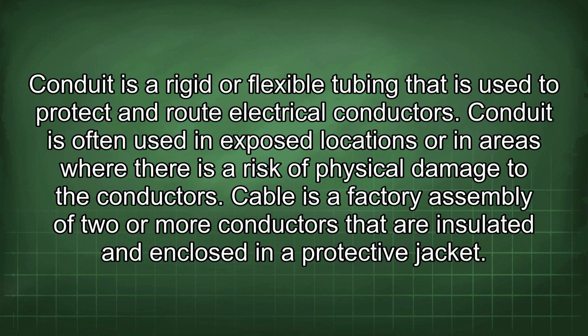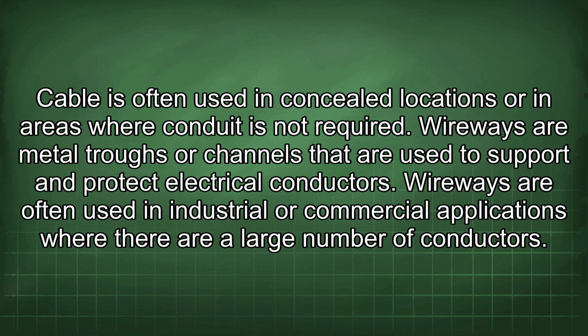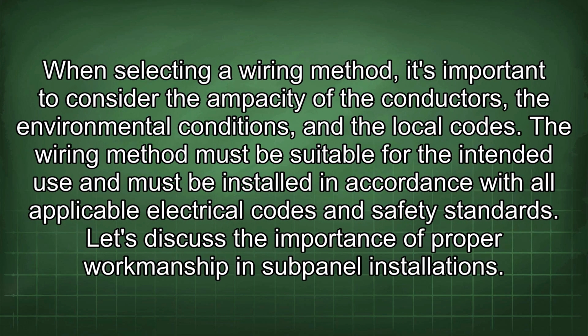Cable is a factory assembly of two or more conductors that are insulated and enclosed in a protective jacket. Cable is often used in concealed locations or in areas where conduit is not required. Wireways are metal troughs or channels that are used to support and protect electrical conductors. Wireways are often used in industrial or commercial applications where there are a large number of conductors. When selecting a wiring method, it's important to consider the ampacity of the conductors, the environmental conditions, and the local codes. The wiring method must be suitable for the intended use and must be installed in accordance with all applicable electrical codes and safety standards.